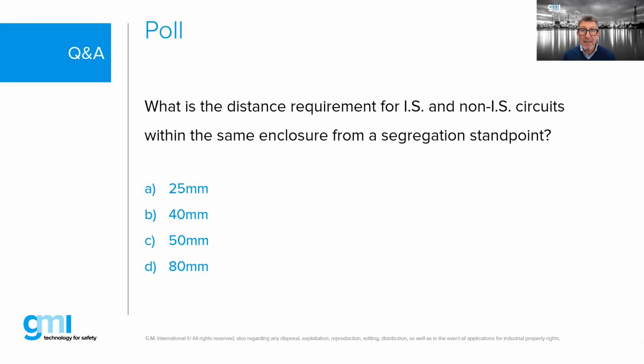It's very important to keep segregation, because you might have a high-power non-IS trunk with high voltages nearby. If there's a short, the wires could melt down, and if that happens next to an IS circuit, you'd bring very high voltages into the hazardous area. There are ways around the segregation distance—shielding cables, using armor—different methods to achieve it, but with unarmored conductors or cables, we do need separate cable trays or enclosures.